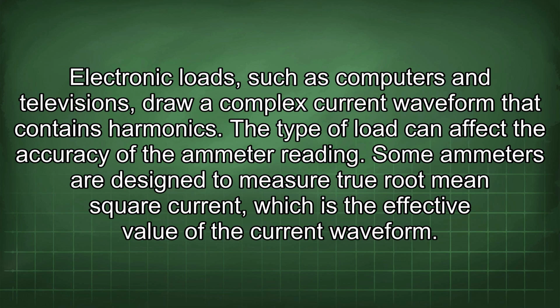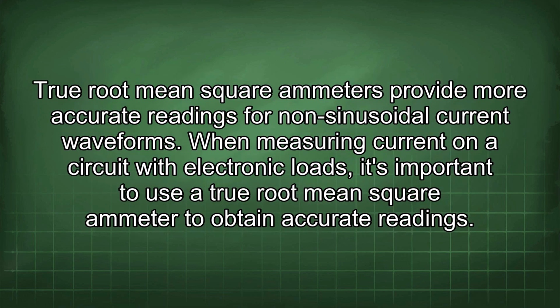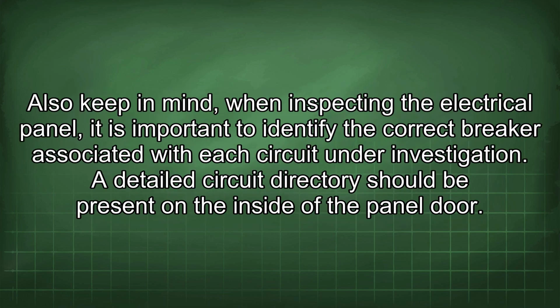Some ammeters are designed to measure true root mean square current, which is the effective value of the current waveform. True root mean square ammeters provide more accurate readings for non-sinusoidal current waveforms. When measuring current on a circuit with electronic loads, it's important to use a true root mean square ammeter to obtain accurate readings. Also keep in mind, when inspecting the electrical panel, it is important to identify the correct breaker associated with each circuit under investigation.